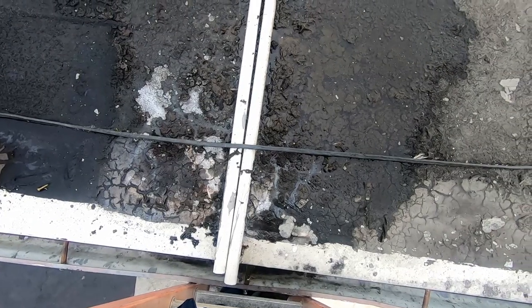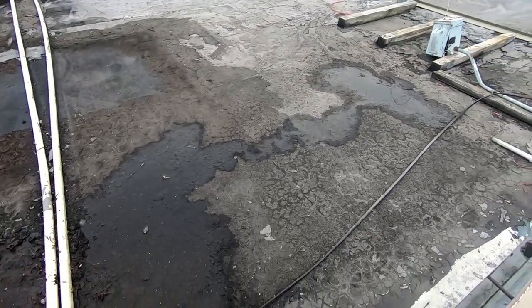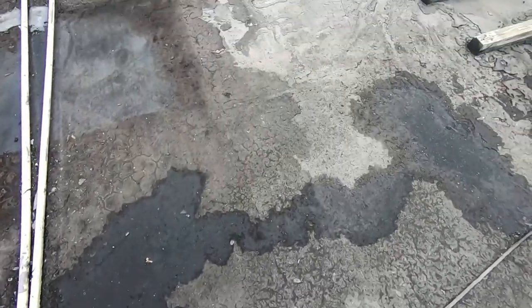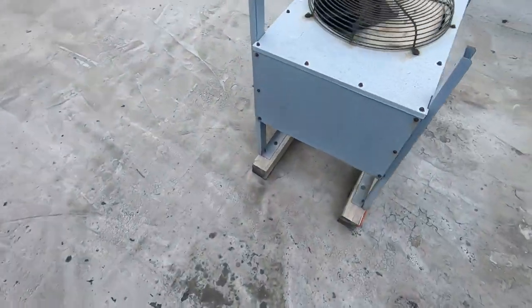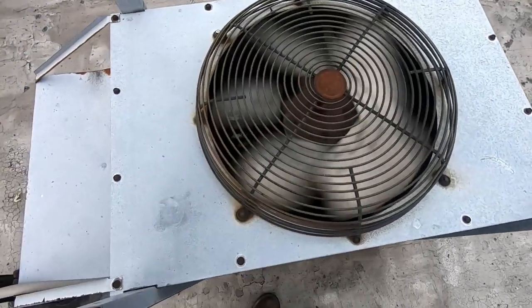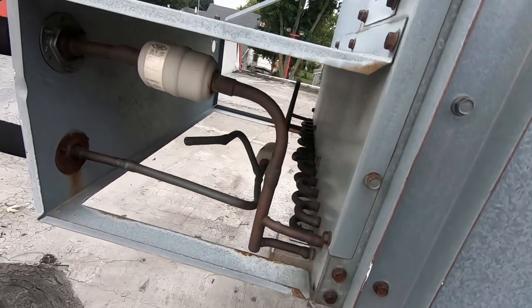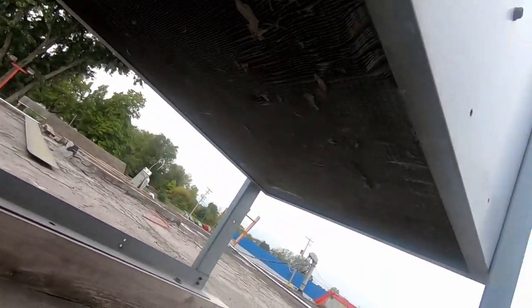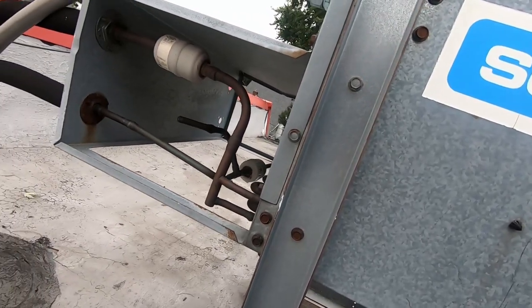Here's one of those things you want to watch out for — grease on the roof. You walk through it and then you track it right onto your ladder, and next thing you know, you're making your rungs slippery. I can see through the coil from the bottom, so it's obviously not too horribly dirty. I've got multiple dryers or mufflers of some sort on this thing. So that's not one of our issues.